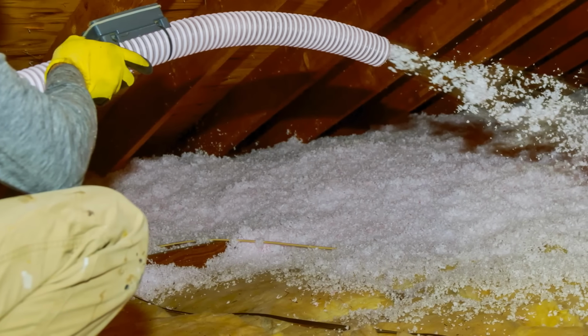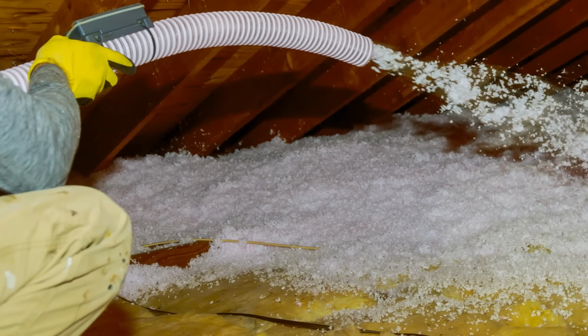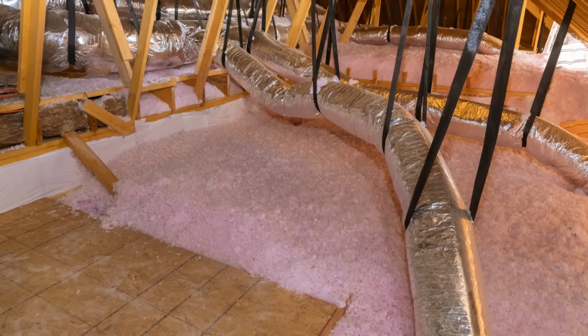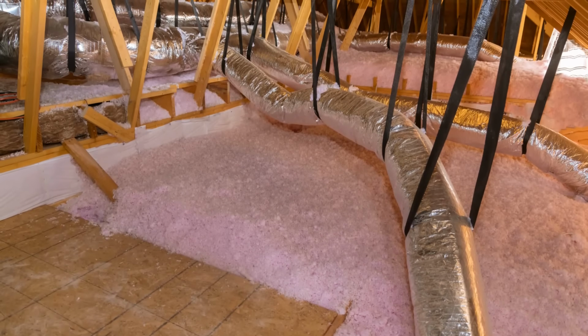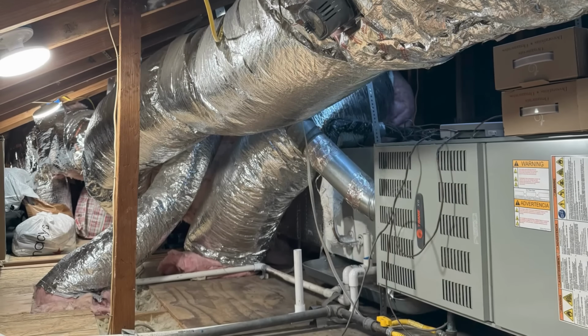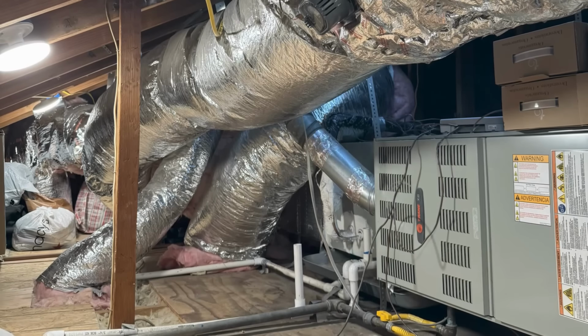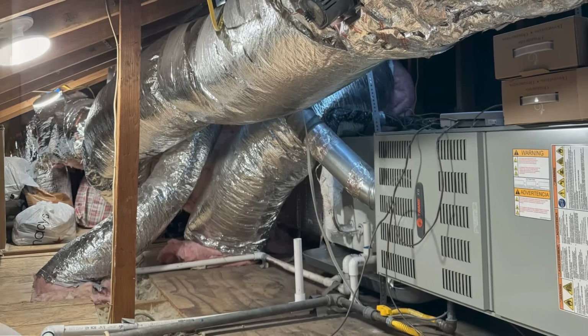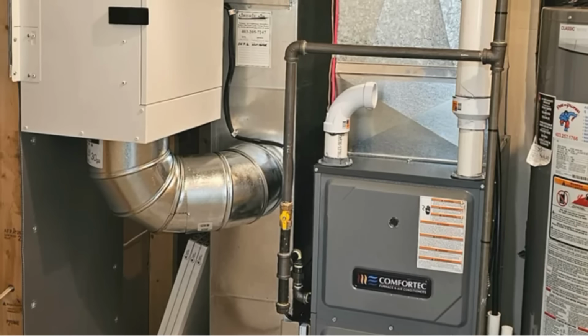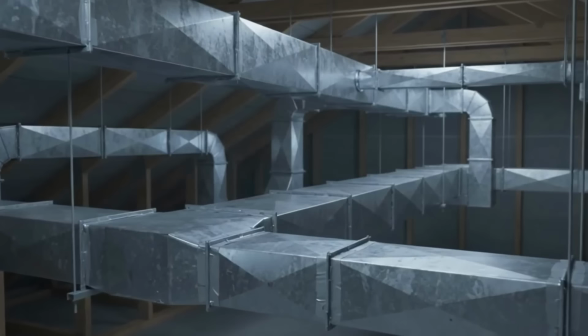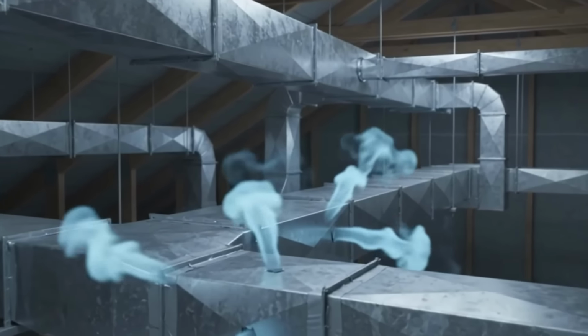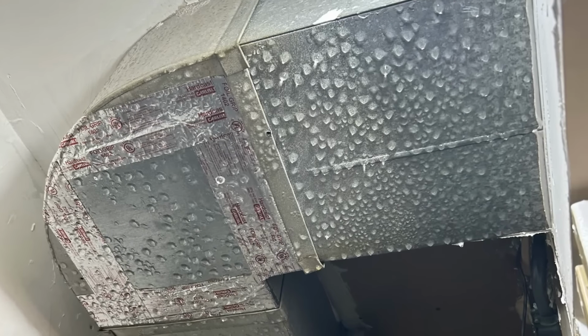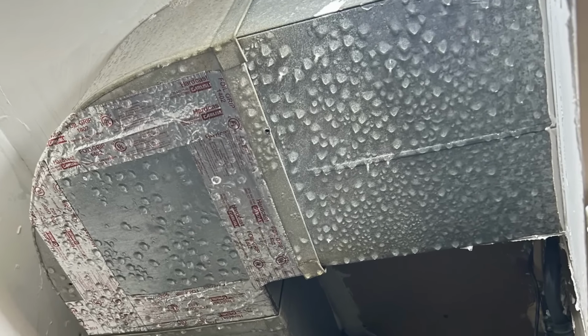While the ceiling is usually insulated to R38 or R49, the ductwork is usually insulated to a meager R6 or R8 if you're lucky. That massive temperature difference leads to heavy thermal losses and immediate energy penalties of up to 30% compared to keeping your ducts and air handler inside the conditioned space, not to mention that duct leakage can exacerbate this problem. But more importantly, this configuration is a severe condensation and mold risk.